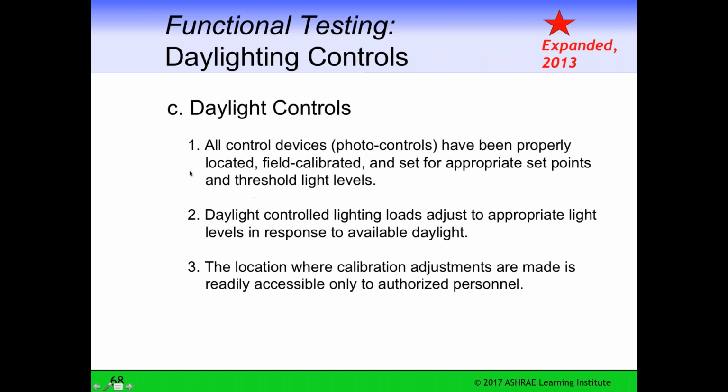And for daylighting control, you have to verify that all control devices have been properly located, field calibrated, and set for appropriate thresholds and threshold lighting levels, and that daylighting control lighting loads actually adjust to the appropriate light levels in response to available daylighting, and that the location where the calibration adjustments are made is readily accessible.